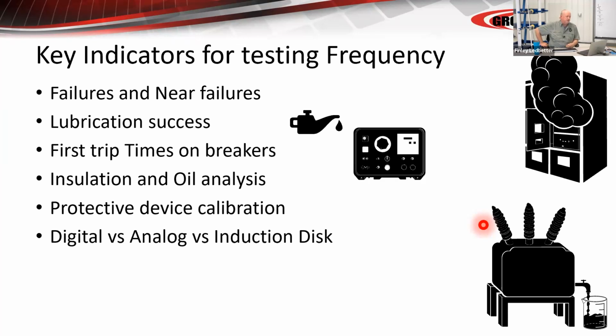Protective device calibration. Do you still have some induction disc or thermal relays? Have you gone completely to digital relays, gotten rid of all of the older electronic relays that were non-discrete? No longer analog, no longer induction disc. You know, there's things you can do to look forward. The new modern relaying, if it goes in and is set up properly and performs right the first 6 months, it's probably going to live a long time. The older analog stuff drifted and died over time, so it aged and died.